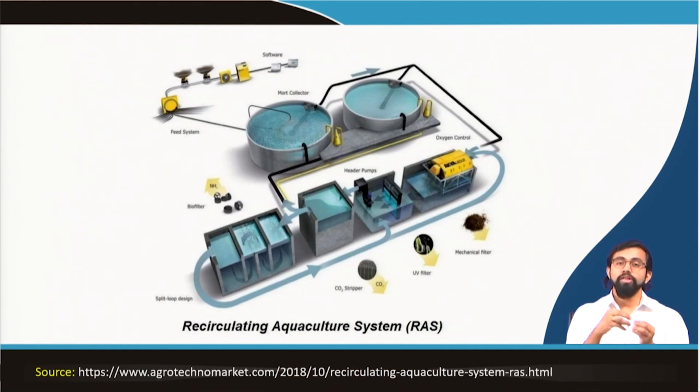Normally we provide different biomedia, like plastic coils. This plastic has a very high specific surface area. Because of enough aeration and the amount of nutrient present in the wastewater, different kinds of nitrifying bacteria will grow on its surface. Not only nitrifying bacteria, but different other types of bacteria will also grow on the surface of these biomedia.